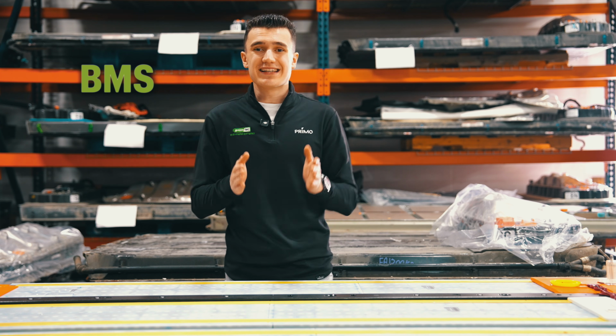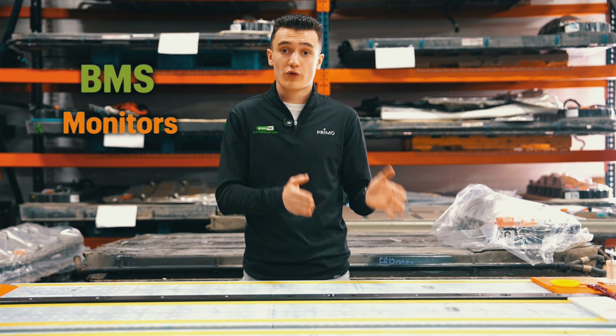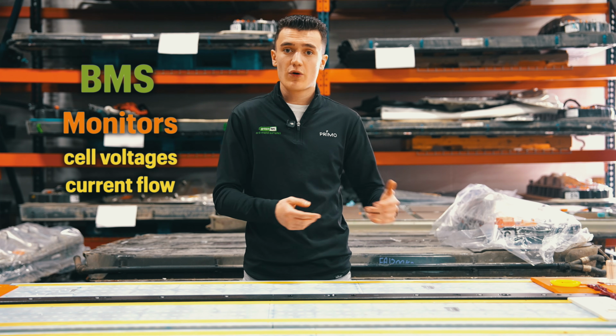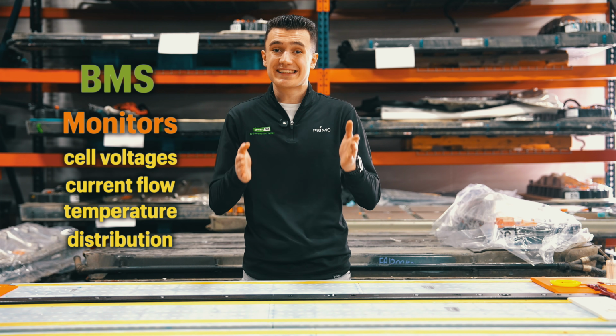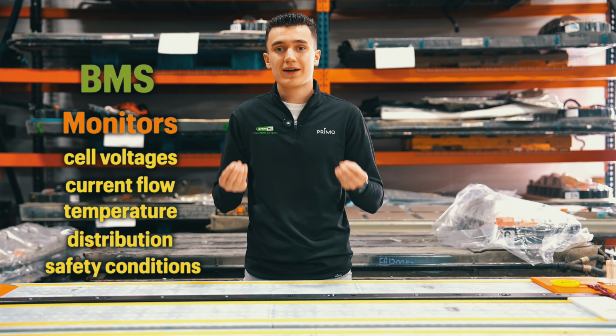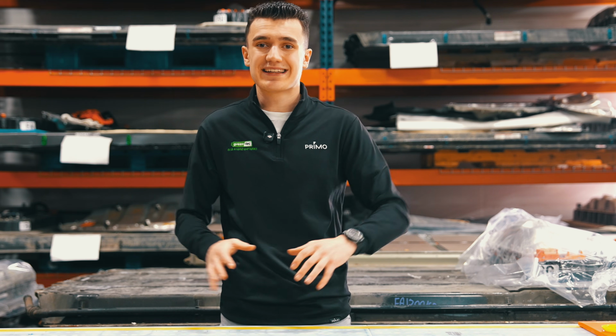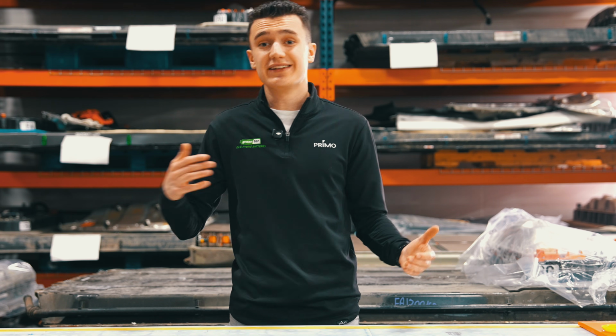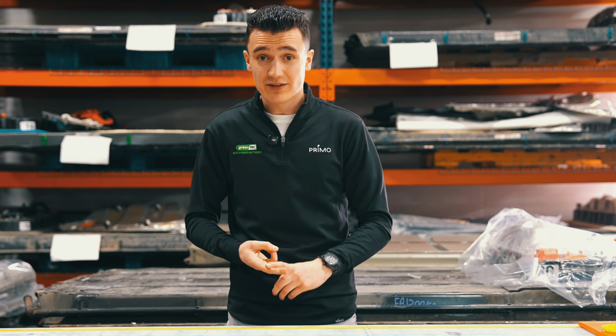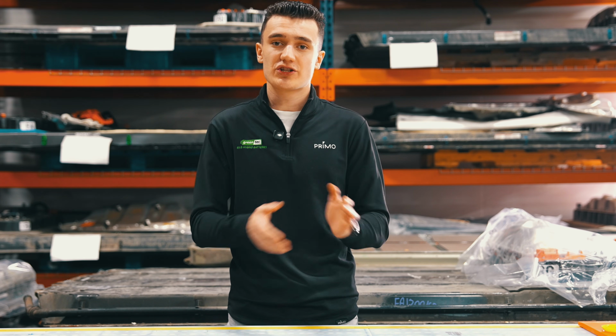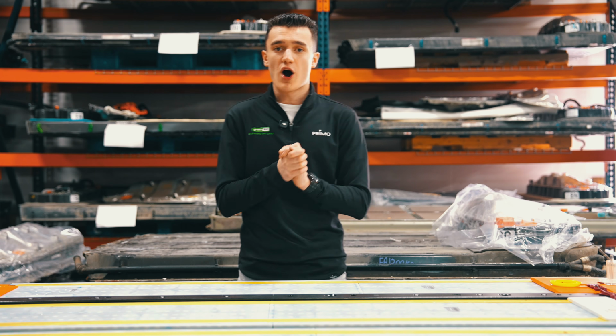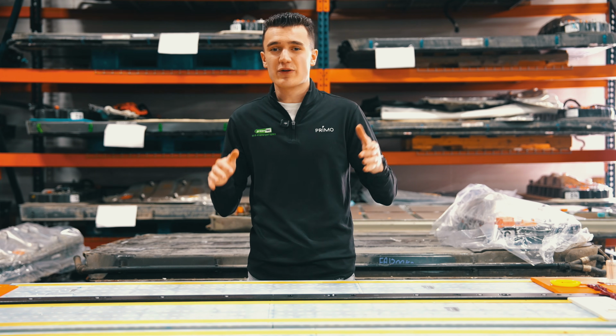So the BMS is continually monitoring grouped cell voltages, current flow, temperature distribution, and safety conditions in real time. It uses that data to actively control charging, discharging, thermal management, cell balancing, and high voltage connections to keep the battery operating safely, efficiently, and within its limits.